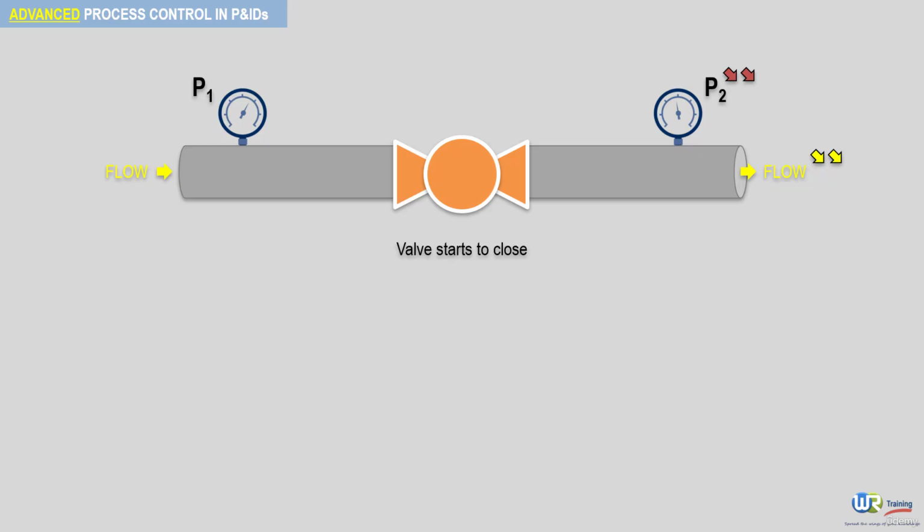It is important to know that even though we say that the control valve on a pipe will decrease pressure and flow, no control valve can drop the pressure to a desired level and at the same time drop the flow rate to a desired level. We can adjust a control valve based only on one of these parameters. We can drop the pressure to a predetermined level, but the amount that the flow rate drops is beyond our control. Likewise, we can drop the flow rate, but the amount by which the pressure decreases is beyond our control.